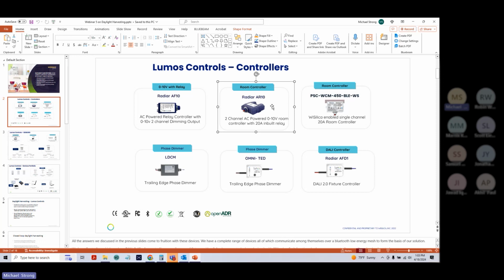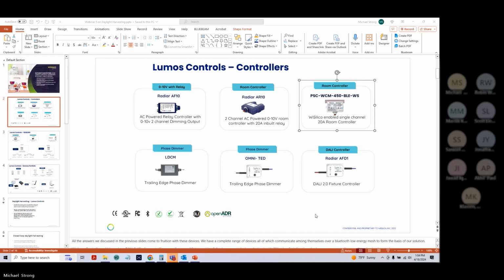You could MacGyver it to make it work as a double dimming device. You could also use this, our single channel, and they are both 16 amp max, actually, using the 80-20 rule. And they both have zero crossover technology, meaning that the inrush of current that is prevalent in LED drivers and LED lighting will be mitigated, and therefore won't affect their lifespan, or freeze relays in place, or do other damage to devices along the path.